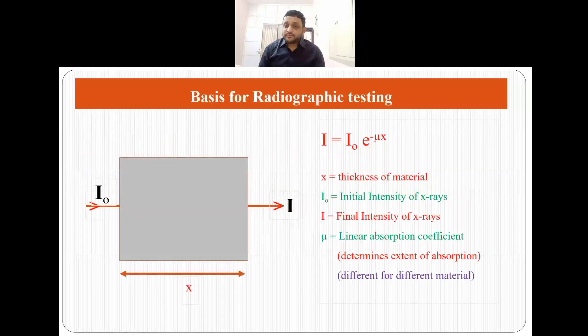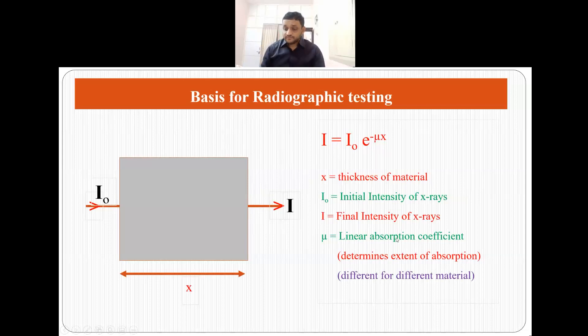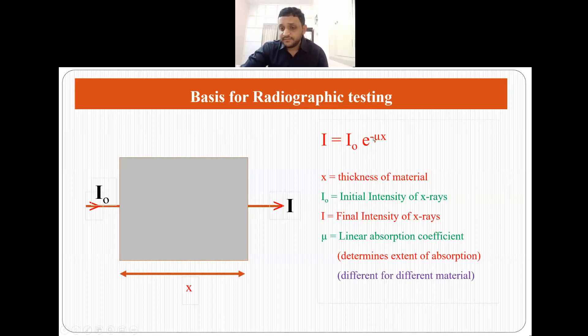The basis for radiographic testing is the intensity of x-rays coming out of the specimen. We calculate that intensity using the formula I = I₀ · e^(−μx), where I₀ is the initial intensity of x-rays, μ is the linear absorption coefficient which determines the extent of absorption and is different for different materials, and x is the thickness of the material the x-rays are passing through. This is how we determine the intensity of the final x-rays coming out of the specimen.